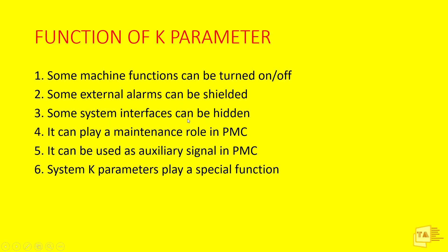Some system interfaces can also be hidden, which I'll show later in this video. The K Parameter can also play a maintenance role in the PMC and can be used as an auxiliary signal in the PMC. For example, for external alarms we can bypass the sensor input. If I'm using input X0.0, instead of X0.0 I'll assign Keep Relay K0.0 and permanently turn on K0.0 — this provides the sensor signal and allows me to bypass and shield the alarm.